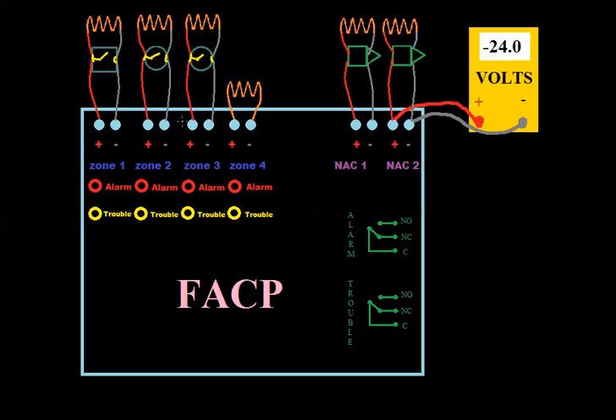As we can see, these are our little alarm lights. None of them are filled in. None of them are in alarm. They're not in trouble. So we know the panel's not in alarm. You can look at the little switches here and see that none of these are shorted. Like we talked about before, a short circuit on a conventional panel is what causes an alarm.